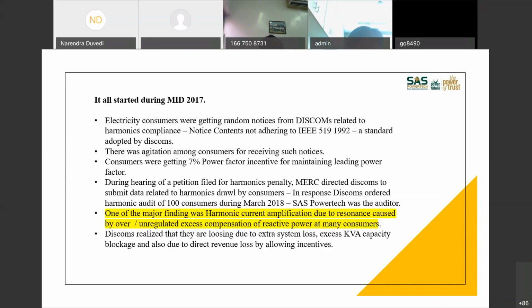Around, say, from 2000 onwards, nonlinear loads increased in tremendous numbers in our industry. All of us started using a lot of VFDs, a lot of UPS systems and all that. And in a typical harmonic environment, capacitors can create havoc. Ultimately it gets turned into resonance and harmonics increase. So the first thing we could tell MSEDCL was the harmonic distortion in 63% of the cases. We saw that the harmonic distortion was increasing because of the introduction of more capacitors than required.